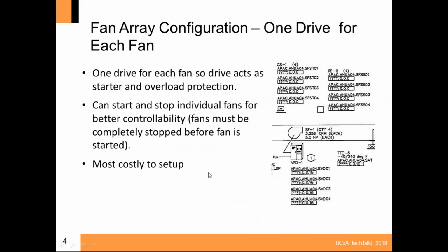The next setup is a drive setup where you can actually have independent VFDs for each fan motor. In this case, we have 4 fans, and each fan has a VFD associated with it. This is probably the most expensive, sweetest setup you can have, because each one of these drives now acts as an overload protecting device on that motor, and on top of that, it's acting as a starter. So you can ramp up each individual fan, or even sometimes look at the energy savings and say, I can save more energy only operating 3 fans instead of running 4 fans at a time.